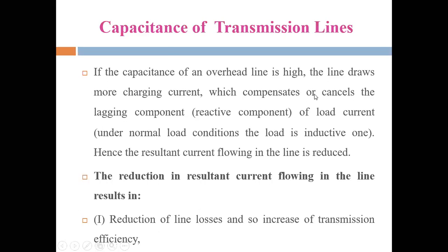This cancels the lagging component, that means the reactive component, under normal load conditions. Hence the resultant current flowing in the line is reduced. The reduction in current reduces the line losses and so increases the transmission efficiency.